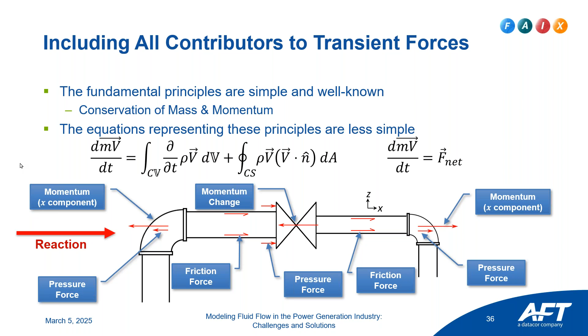So if we go forward, this is an example from a publication in 2015, ten years ago, from a couple of gentlemen I actually had a chance to meet. They worked for an engineering firm in Chicago, and they presented this case study on a flow of 1,000 psi, about 7,000 kilopascals, steam supply going through piping to a turbine supply. There's a turbine stop valve that closes, and when it does, it generates loads in the intermediate piping.